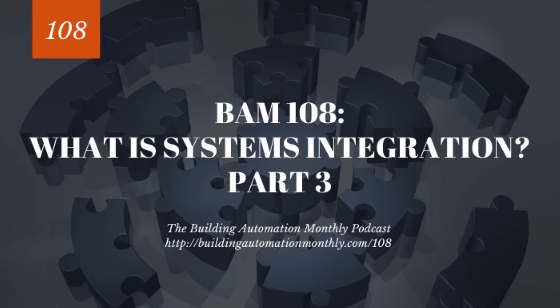Usually you'll have the programming capabilities if you're doing this. Only a handful of times have I seen folks try to take this on without having the skill set to go about implementing these kinds of integrations. With that being said, very rarely is the support structure put in play. And then finally, what systems do you have? This is always an interesting one because one, you want to make sure your BAS has a way to consume APIs or to at least let you write programs to consume APIs. But then you want to make sure that the API actually has the data points you need. So those are kind of what systems.